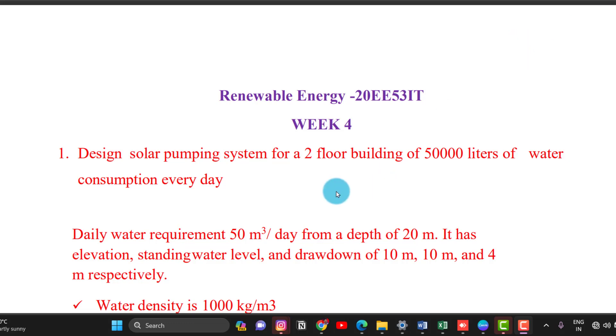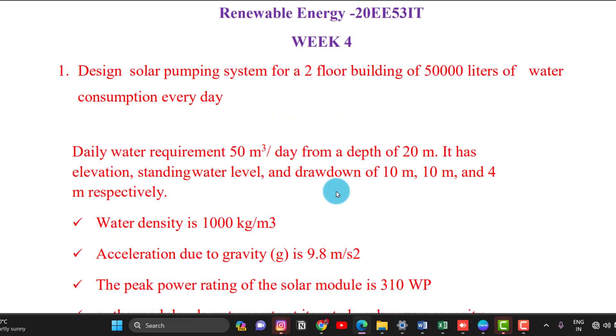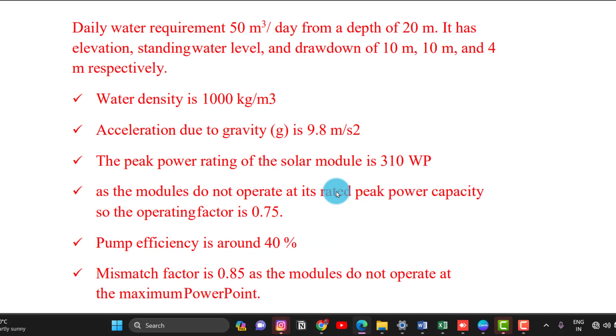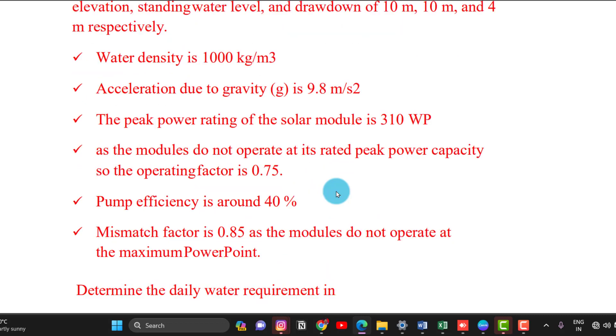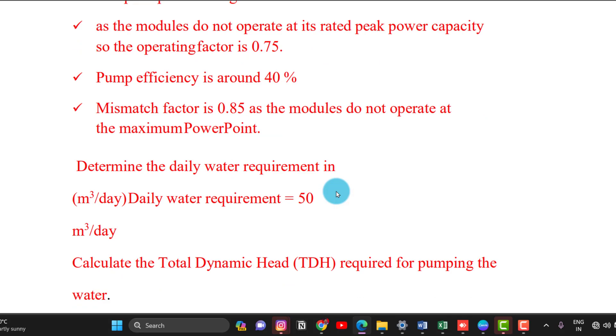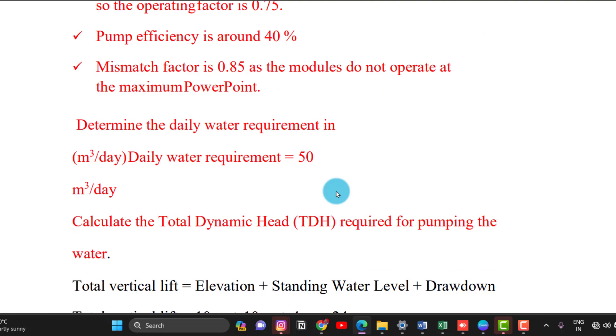The first example: design a solar pumping system for a 2-floor building with 50,000 litres of water consumption every day. Daily water requirement is 50 m³ per day from a depth of 20 m. It has elevation, standing water level, and drawdown of 10 m, 10 m, and 4 m respectively. Water density is 1000 kg/m³, gravity 9.8 m/s². Peak power rating of solar module is 310 Watt peak, operating factor 0.75, pumping efficiency 40%, and mismatch factor 85%. Determine the water requirement in m³ per day and calculate the total dynamic head.